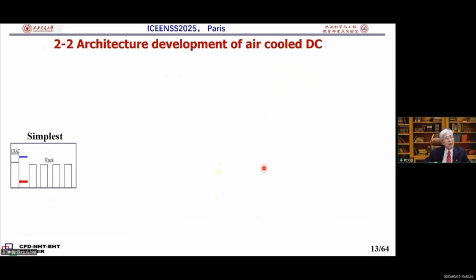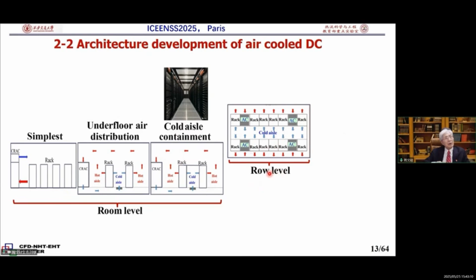In recent years, the air-cooled data center has developed in the following 3 stages. At the early stage, we call it room level cooling. From a very simple situation to underfloor air distribution to closed aisle, cold aisle, we can call it containment, like this one. This is a typical data center structure of cold aisle containment. Then with the increase of the scale of the data center, the big air conditioner is divided into several small air conditioners, which sit between different racks. We call this row level cooling.